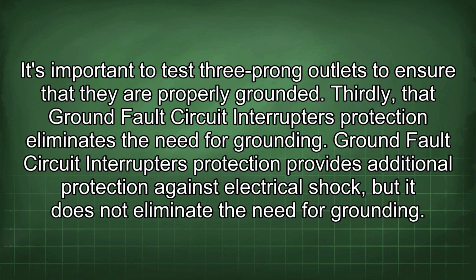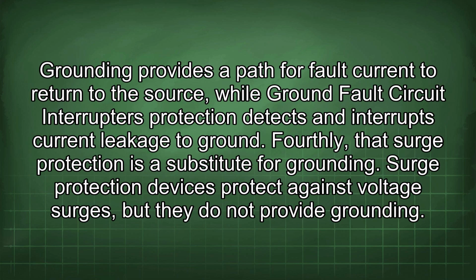Thirdly, that ground fault circuit interrupter protection eliminates the need for grounding. Ground fault circuit interrupter protection provides additional protection against electrical shock, but it does not eliminate the need for grounding. Grounding provides a path for fault current to return to the source, while ground fault circuit interrupter protection detects and interrupts current leakage to ground.